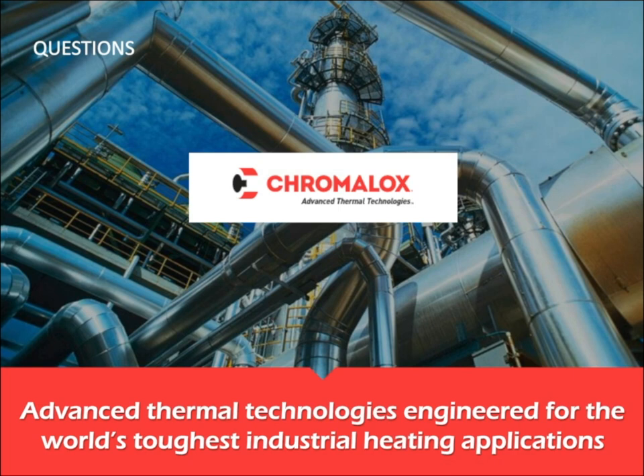Some of the other ones, just off the top of my head too, we've had some propane superheaters for natural gas on offloading facilities where they need to vaporize some of the systems. And then probably the more recent one, the last one I could think of, is we've had a heat transfer system where we're heating hot oil that's used to refine through a heat exchanger for crude oil in a refinery to heat it up for pumping. So again, we really have a wide variety of applications, just anywhere you're going to use heat. And so obviously there's a lot of industries that can use electric heat there.